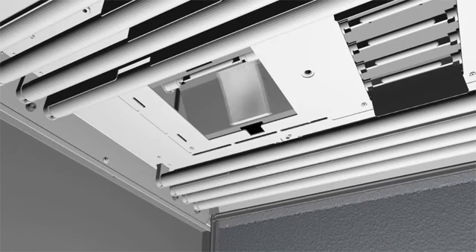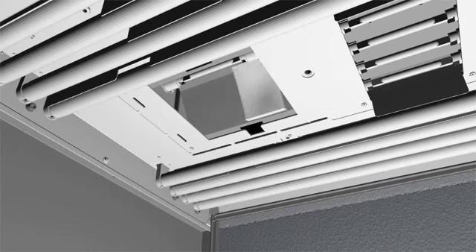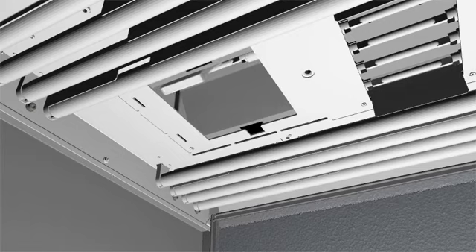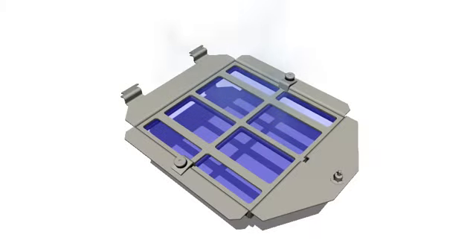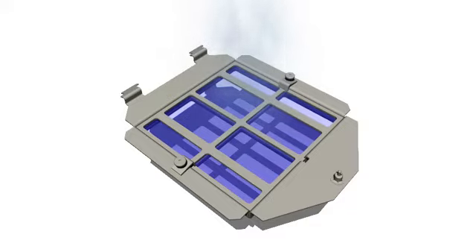Next, dampen a clean cloth with warm water and an ammonia-based window cleaner and wipe any dirt from the daylight lamp reflectors. The daylight filters must be completely dry before you use the unit. Moisture can damage the filter when heat is applied.